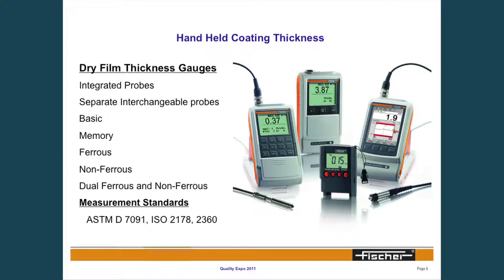One of the most common test methods are handheld dry film thickness instruments. These are used for determining paint or powder coating thickness, and they come in the form of integrated probe instruments or probes on a cable. They are also available in basic instruments or instruments that provide memory and documentation. Depending on the specific application determines which instrument you would select.